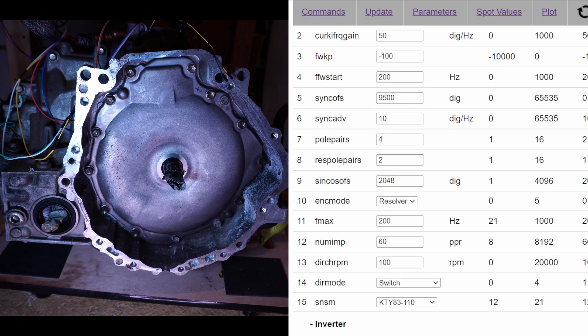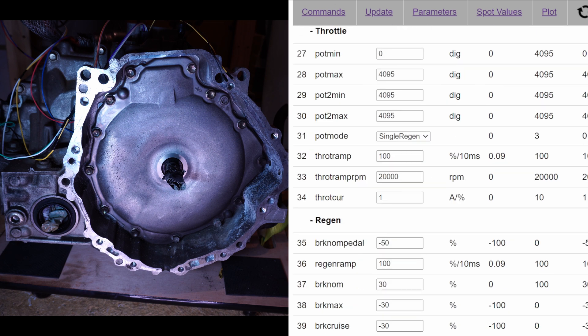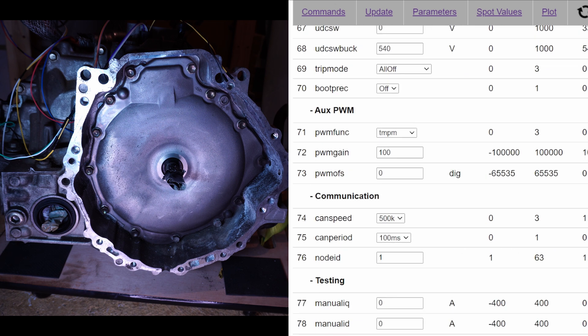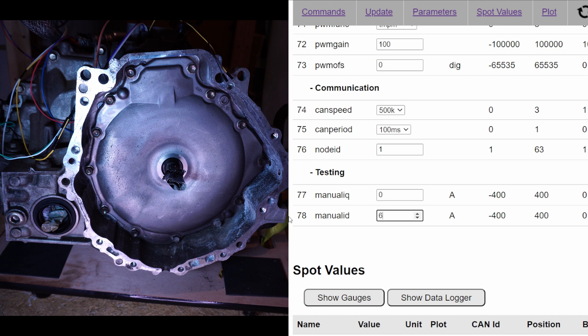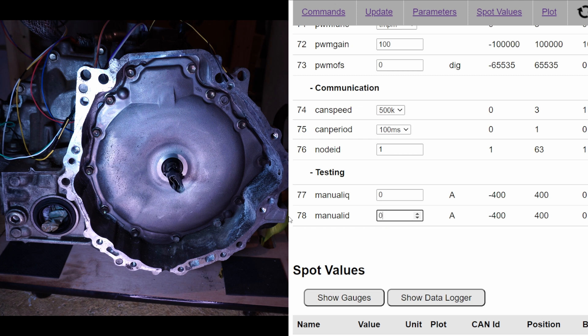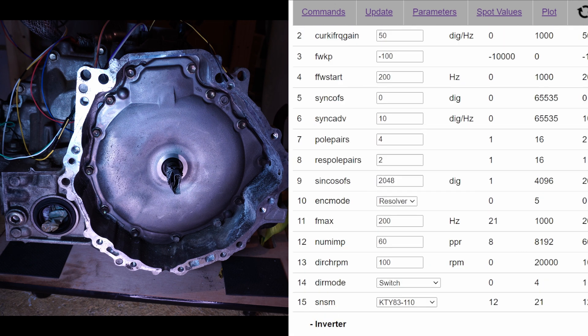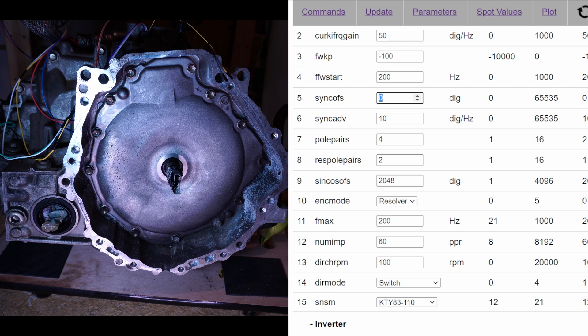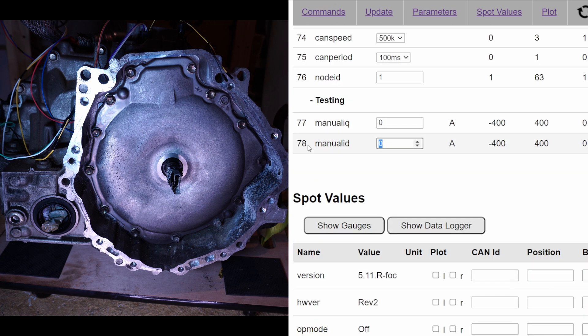I've just started inverter in manual mode. I'm starting from sync-offset 0. The idea is we're going to increase manual ID values, see how our motor reacts. Manual ID 4, there is no movement. Manual ID 6, and now we have movement. The idea is we're going to increase the sync-offset number. Sync-offset now is 0. We're going to go to 1000. Once we increase sync-offset, we're going to see that we need more and more current for manual ID to be able to turn our motor.